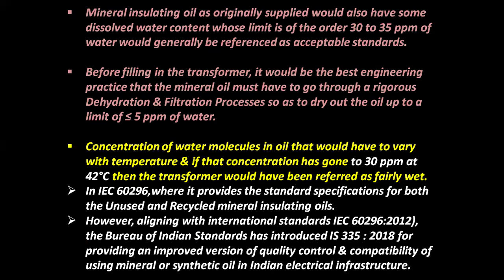Concentration of water molecules in oil varies with temperature, and if that concentration has gone to 30 ppm at 42 degrees centigrade, then the transformer would be referred to as fairly wet. Most important, again, I repeat, if that concentration has gone to 30 ppm at 42 degrees centigrade, then the transformer would be referred to as fairly wet.